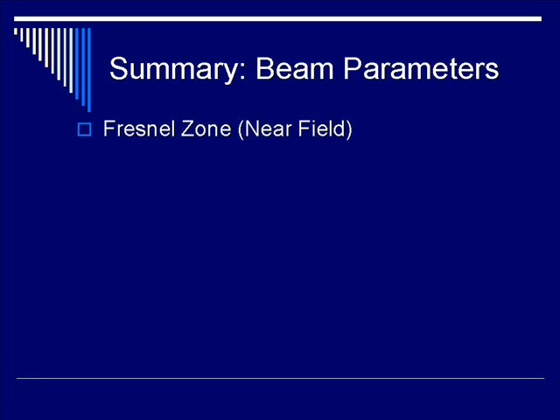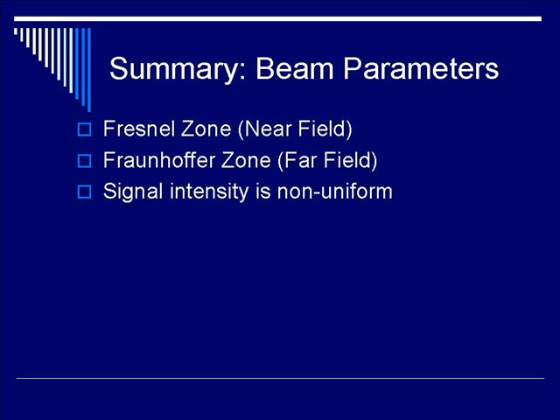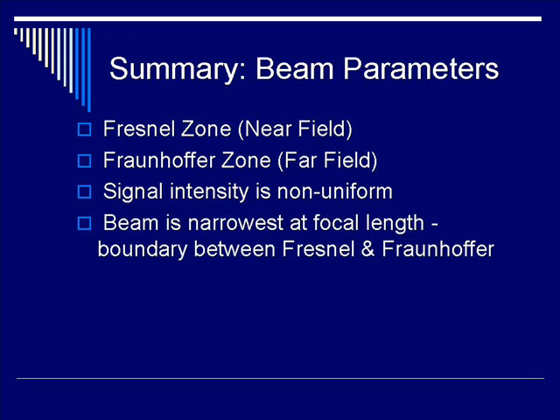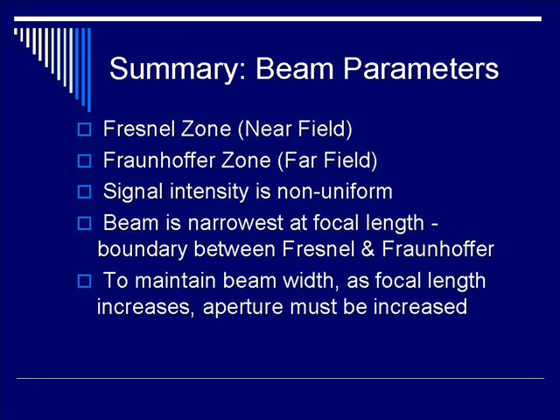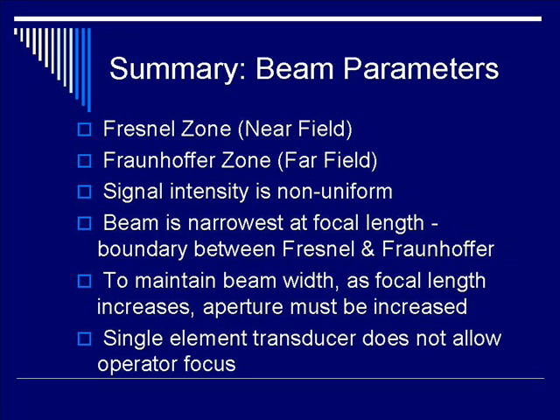In summary, the beam profile contains the Fresnel zone, which is the near field, and the Fraunhofer zone, which is the far field. Signal intensity is non-uniform across the beam, and the beam is narrowest at the focal length — the boundary between the Fresnel and Fraunhofer zones. To maintain the same beam width across the profile, as the focal length increases the aperture must be increased. This is comparable to the F-number concept in photography — as focal length increases, you must increase the lens aperture to keep the F-number constant. Finally, single element transducers do not allow for operator focus.